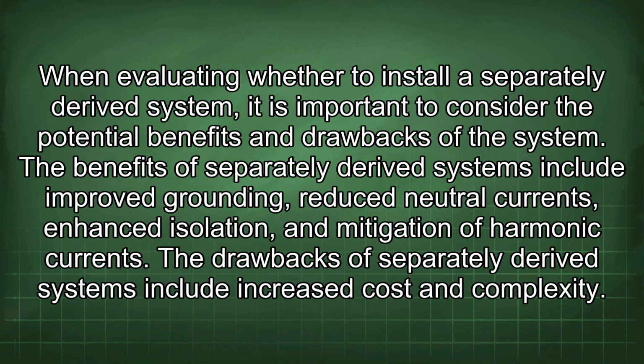When evaluating whether to install a separately derived system, it is important to consider the potential benefits and drawbacks of the system. The benefits of separately derived systems include improved grounding, reduced neutral currents, enhanced isolation, and mitigation of harmonic currents. The drawbacks of separately derived systems include increased cost and complexity.